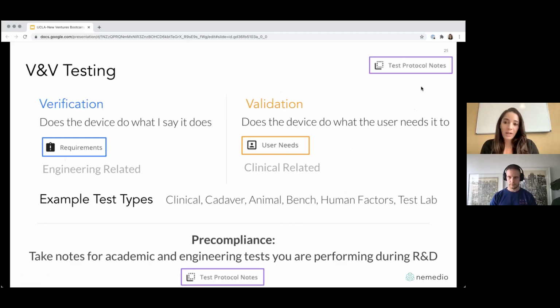During pre-compliance, we lump testing together into one concept called test protocol notes. In full compliance, there are two major types of testing. They're called verification tests and validation tests. Verification tests usually check your requirements and check, does the device do what you designed it to do properly? So if you say the device shall have a power supply separate from its on and off switch, you would check it by inspecting your design to make sure that there are actually two separate things. If you say that the device weighs no more than 10 pounds or is battery operated, you must design a verification test to test that it's being done properly. If you design your device to meet an electrical safety standard, remember that ISO 60601-1 electrical safety standard from before, you must verify that your device meets that standard.